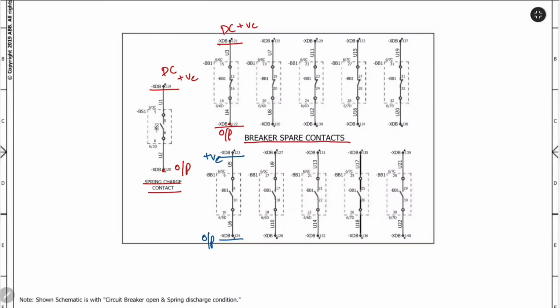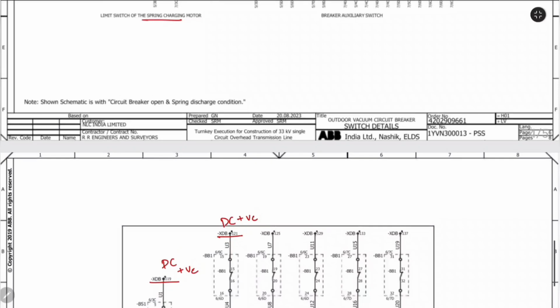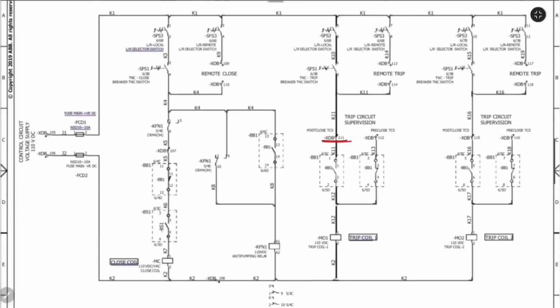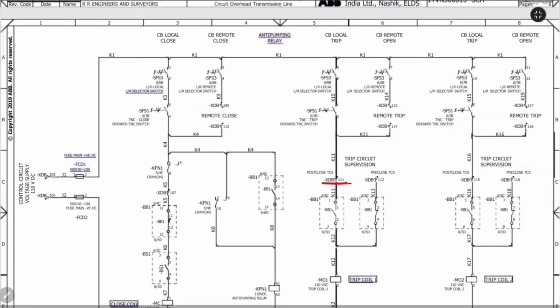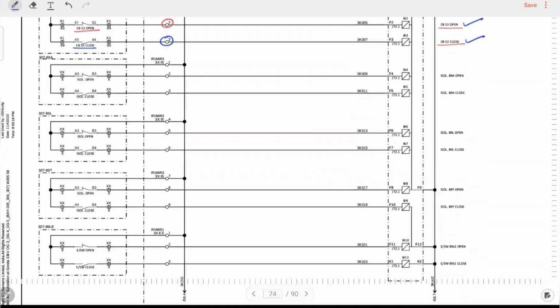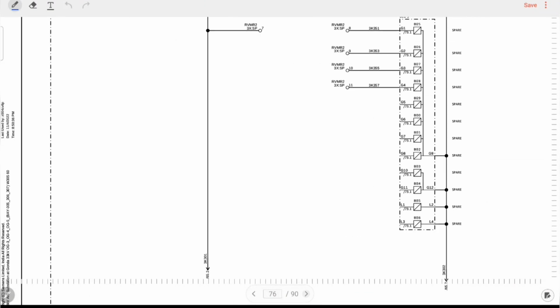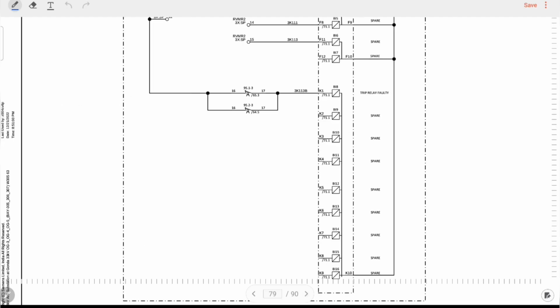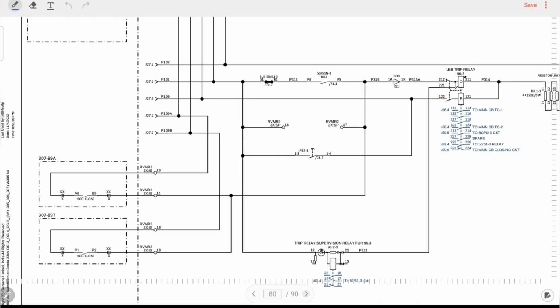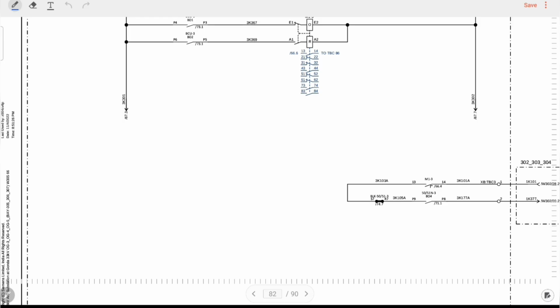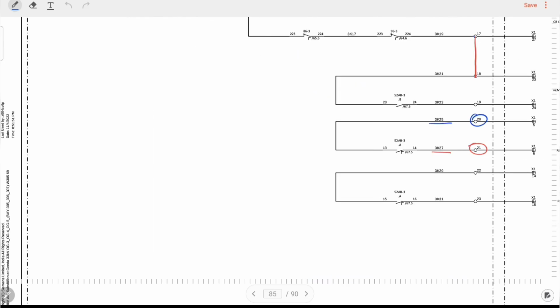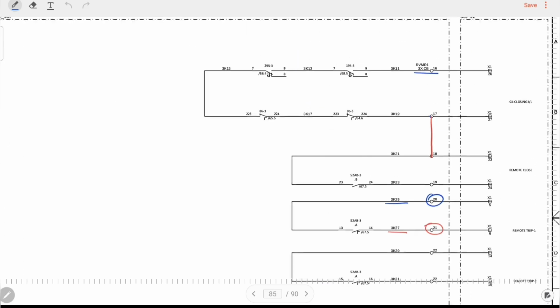And that's the complete control and protection interconnection between an ABB 33 kV vacuum circuit breaker and a Siemens Feeder Protection Panel. By understanding the AC supply, DC control circuit, local operation, remote operation, protection tripping, trip circuit supervision, and status indications one step at a time, commissioning and troubleshooting become much easier.